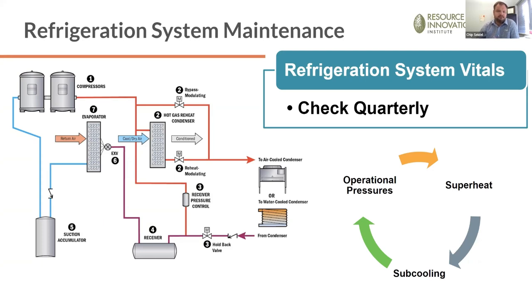These same types of refrigeration checks need to be done on all refrigeration systems. Again, if you've gone the route of air conditioners and independent dehumidifiers, you may have 4 of those in each of your rooms, 4 dehumidifiers. Each of them is going to need to be checked. So it starts to become a more onerous task when you go that route. These should be checked quarterly, ideally, and that's the best way to move forward. Next slide.